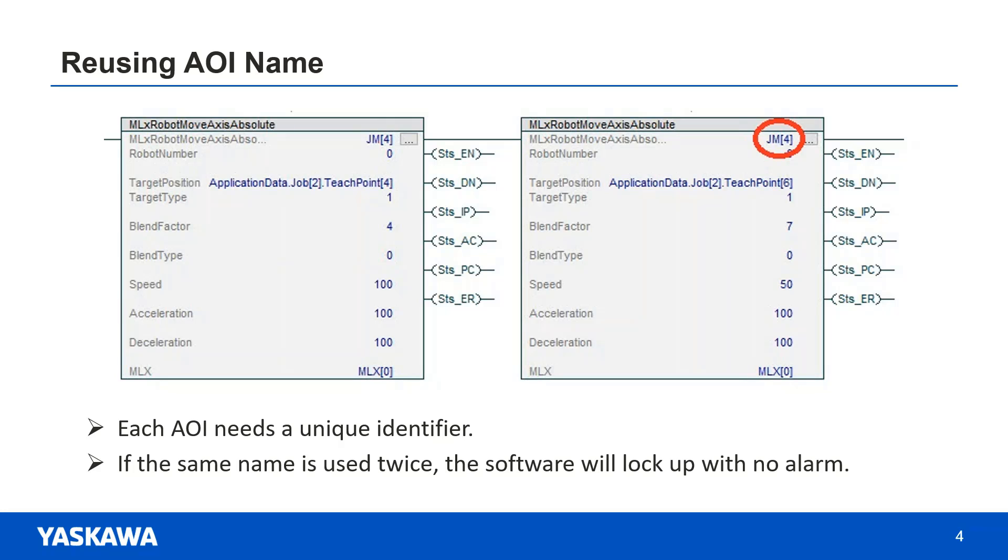The reason for this is every AOI has a special enable false condition that resets its state whenever it's not enabled. This will prepare it for the next time it is called. If you use the same AOI name twice, it will attempt to execute the instruction in one location and attempt to reset the instruction in another location. This will lead to an unresponsive behavior from the system and the command buffer will fill up.